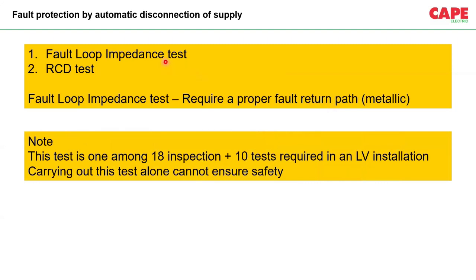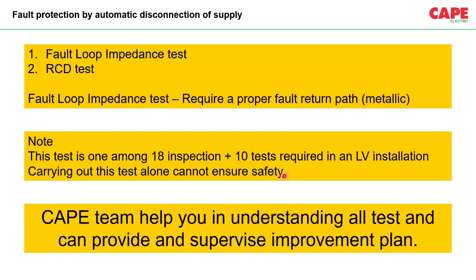Also, please note that this test, protection by automatic disconnection of supply, is one among 18 inspection points and 10 tests. That means 18 plus 10, out of 28. This test is one of them in a low voltage installation. Please note that carrying out this test alone cannot ensure safety. Thinking that the circuit is safe only by doing the fault loop impedance or RCD test is not correct. So this is one among the 28 requirements. Please keep this in mind.